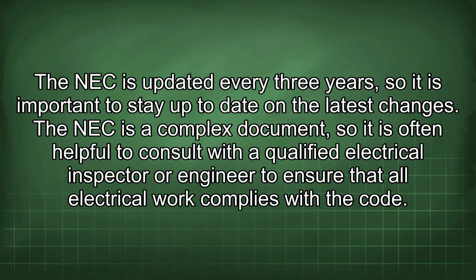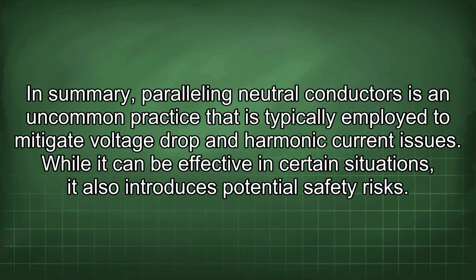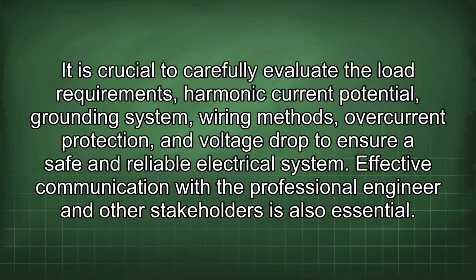The NEC is updated every 3 years, so it is important to stay up to date on the latest changes. The NEC is a complex document, so it is often helpful to consult with a qualified electrical inspector or engineer to ensure that all electrical work complies with the code. In summary, paralleling neutral conductors is an uncommon practice that is typically employed to mitigate voltage drop and harmonic current issues. While it can be effective in certain situations, it also introduces potential safety risks. It is crucial to carefully evaluate the load requirements, harmonic current potential, grounding system, wiring methods, overcurrent protection, and voltage drop to ensure a safe and reliable electrical system.